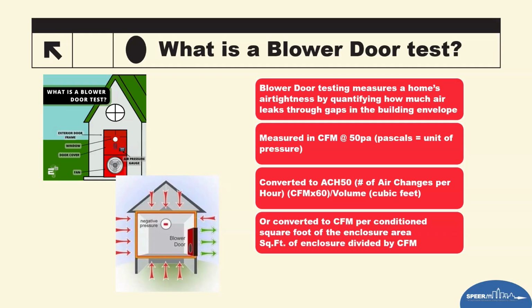That CFM target also varies depending on what pathway you're using, and in the code book, that's what it will say. I'm not going to go through all of that. There are some exceptions written into the 2021 and newer code cycles going forward. That basically is for apartments in R2 buildings and any house or dwelling that's 1,500 square feet or smaller. What we started seeing is rental property being built, and it's just shrinking the square footage. Some of them are less than 1,000 square feet.